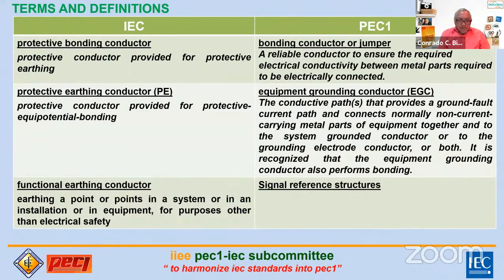There's an additional one called the functional earthing conductor. There are two types of earthing in an installation: protective purposes and functional earthing. Functional earthing is a point or points in a system, installation, or equipment for purposes other than electrical safety - for example, the function of electronic devices with data requirements, like shielded cables used for industrial communications.